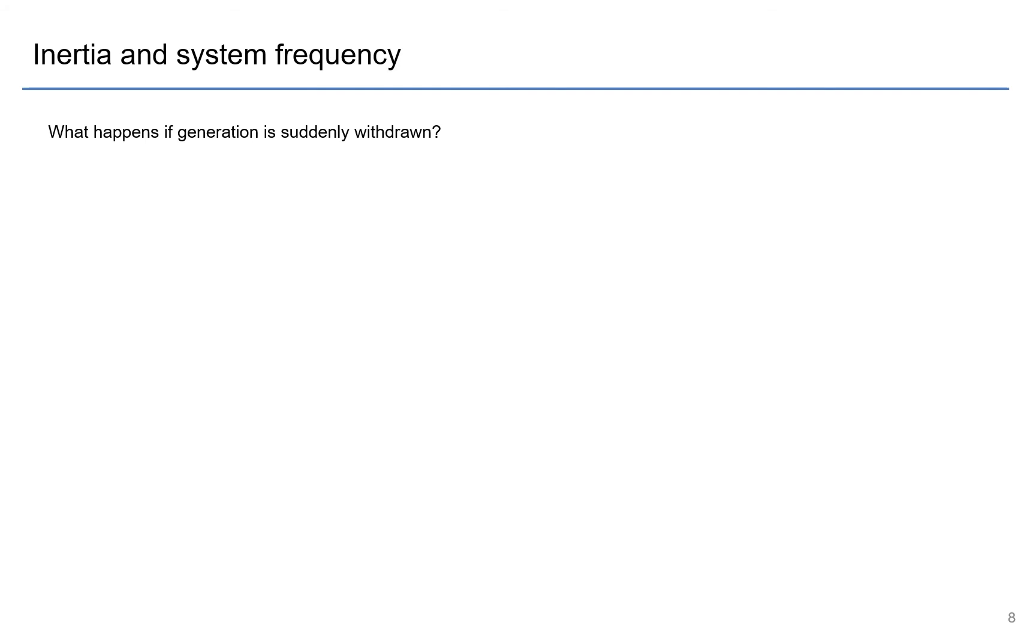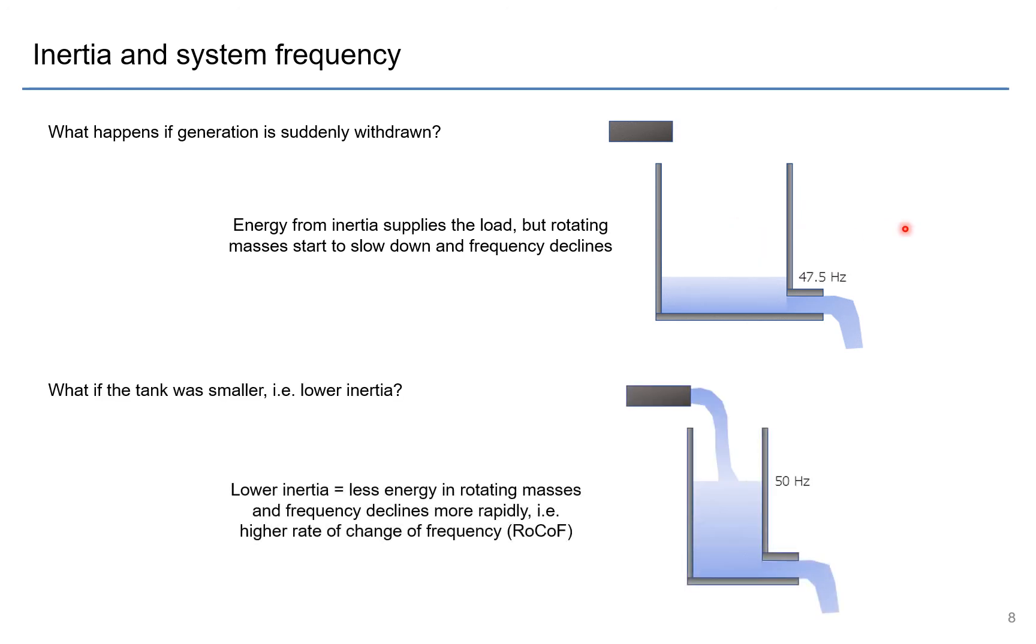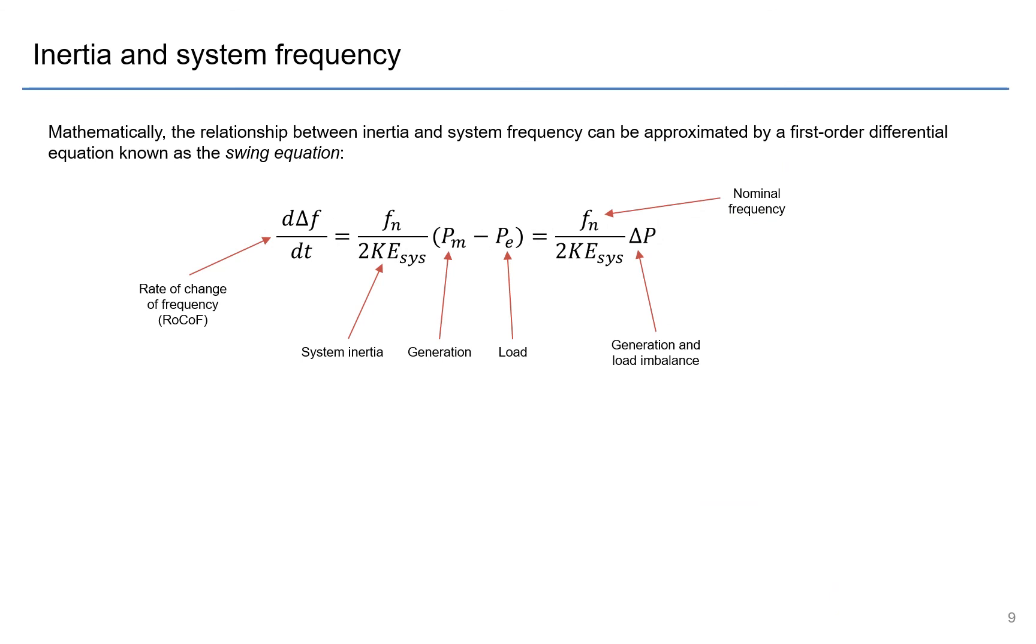So what happens if generation is suddenly withdrawn from the system? You have a situation now where the water stops and the inertia is supplying all the load, and therefore your frequency is declining. But what if the tank was smaller, we had lower inertia? Then the inertia is still supplying the load but the tank is smaller so it drains more quickly, and so you have a faster decline in frequency, so what's called a higher rate of change of frequency, ROCOF.